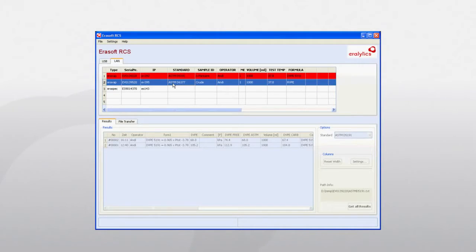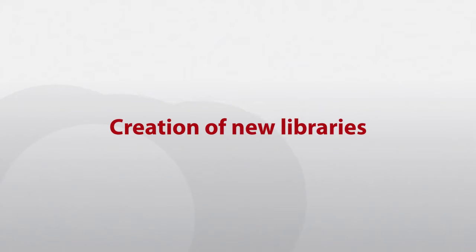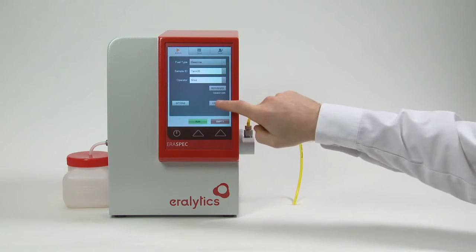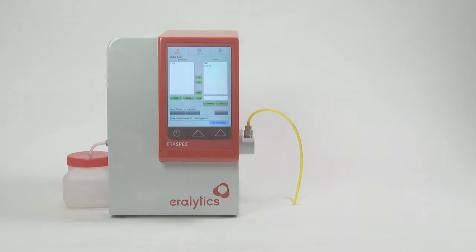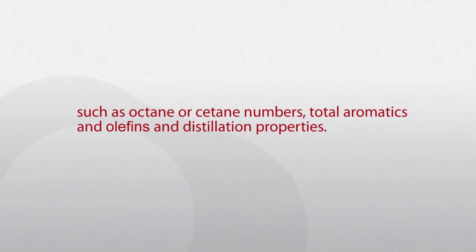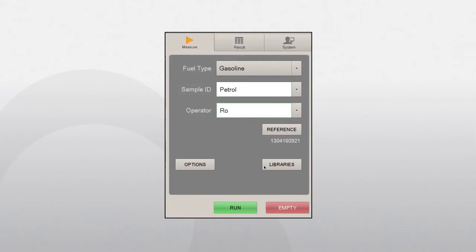Creation of new libraries: To create new libraries, go to the Select Libraries option in the measure menu. Eraspec uses a library or database to calculate results for complex parameters such as octane or cetane numbers, total aromatics and olefins, and distillation properties. The libraries store the spectra of typical samples together with the known values of these parameters as determined by the respective reference methods.